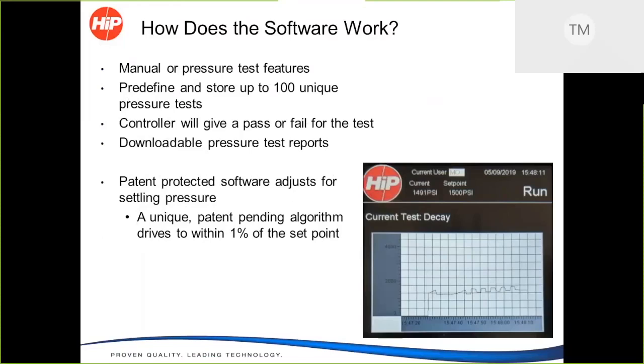We also, because this is an automated system, track all the data from that test. So when we're running a pressure test, we'll track all the pressure versus time data, and then at the end of that test, we'll save that data, and you can actually download that off the unit and print out either a paper copy or an electronic copy of a test report certifying that your test unit has been completed.